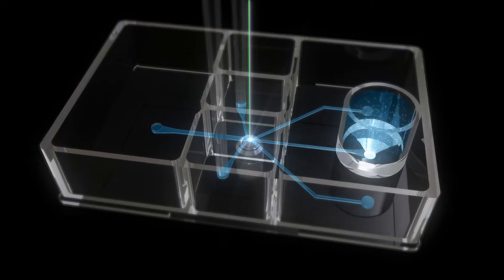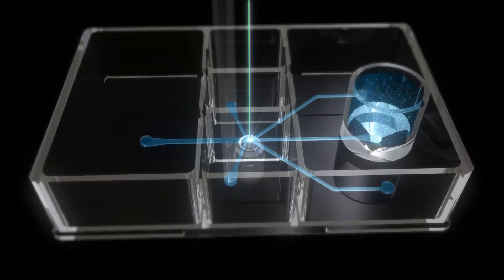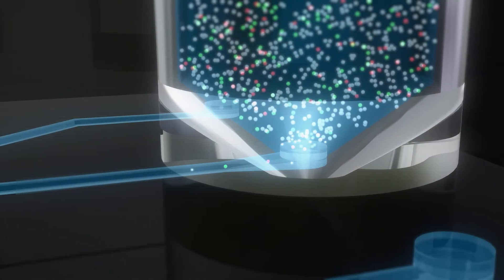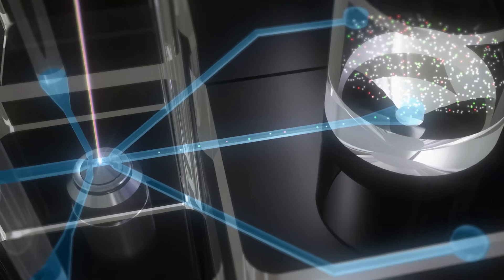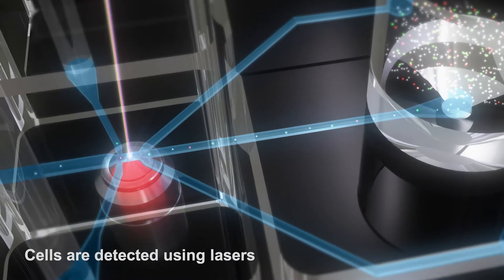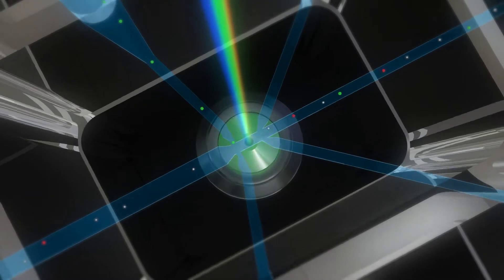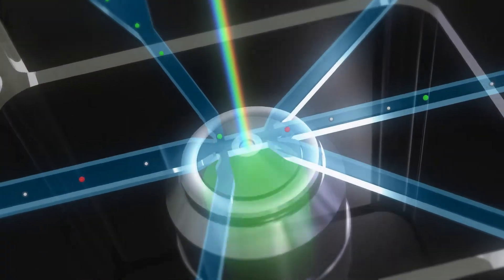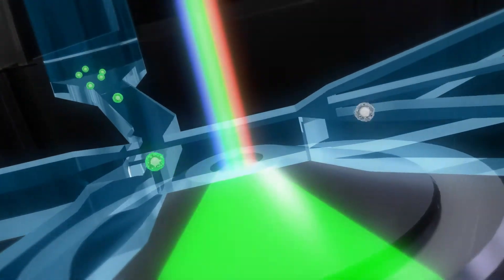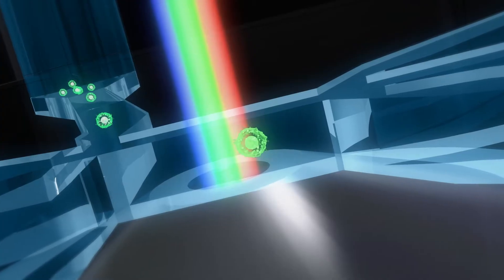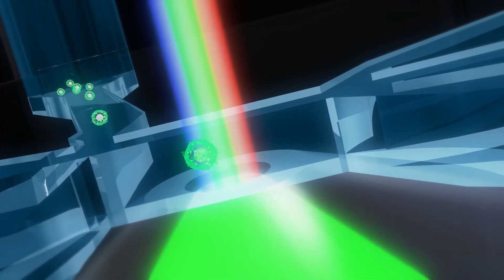When measurement is started, the sheath fluid and sample begin to flow down from their respective reservoirs, and the cells are irradiated by lasers. When a cell is irradiated, fluorescence and scattered light are generated, and these are measured by detectors under the chip.